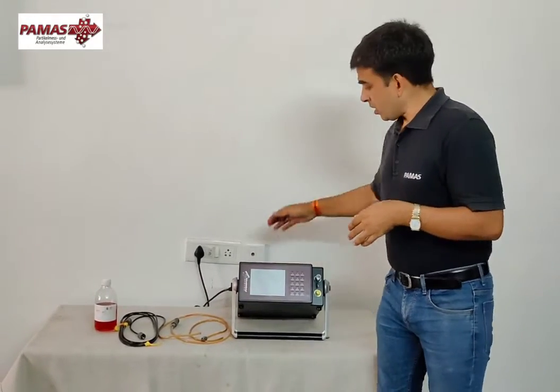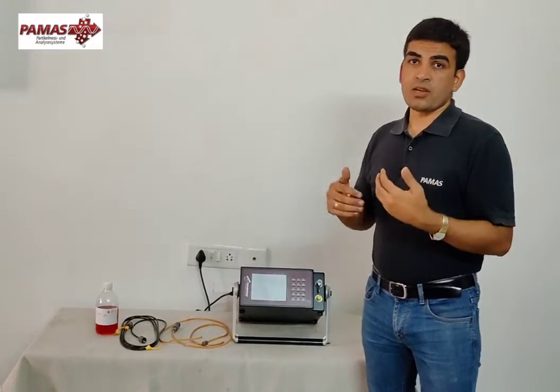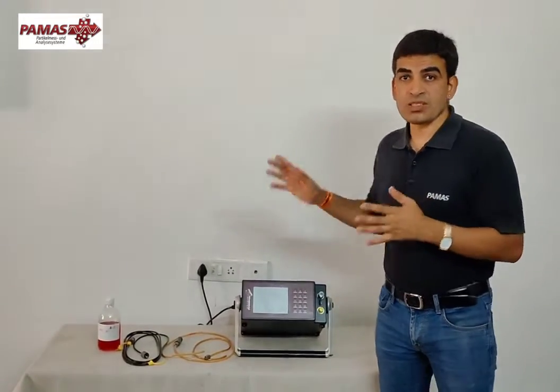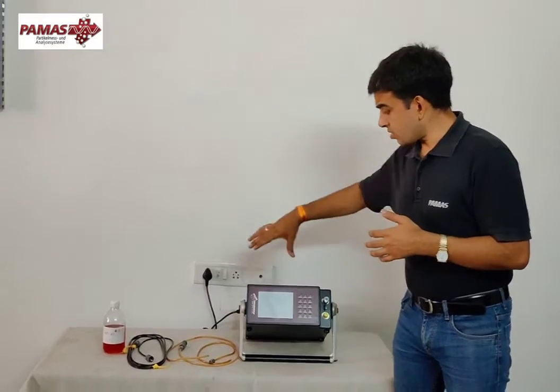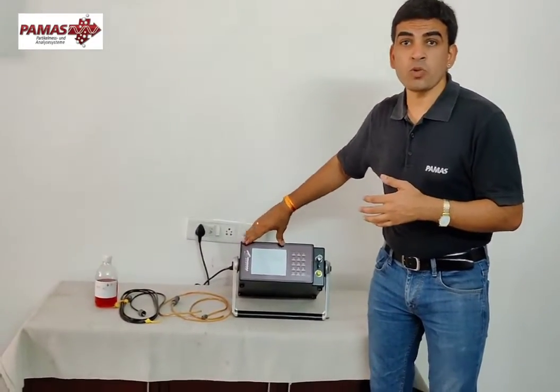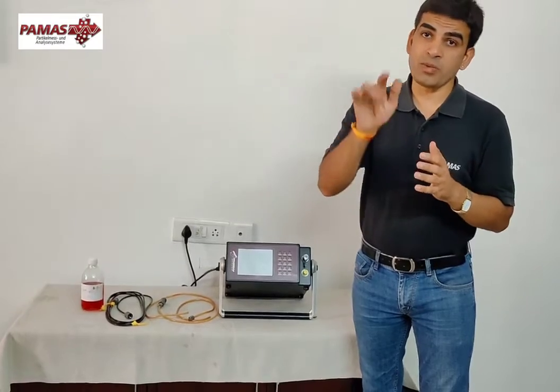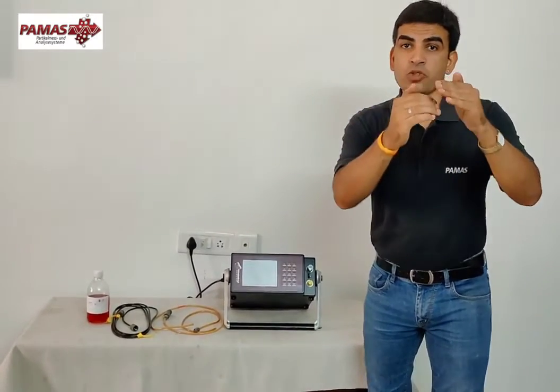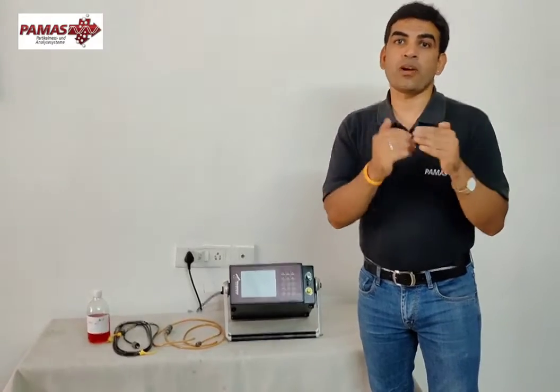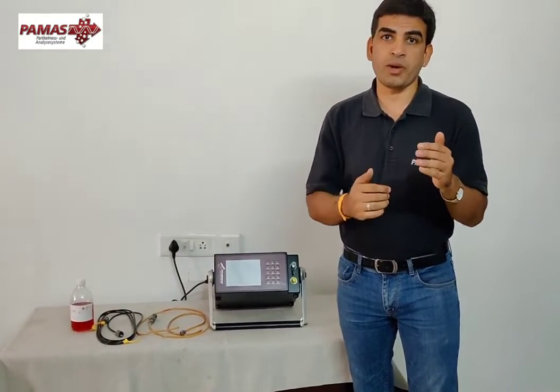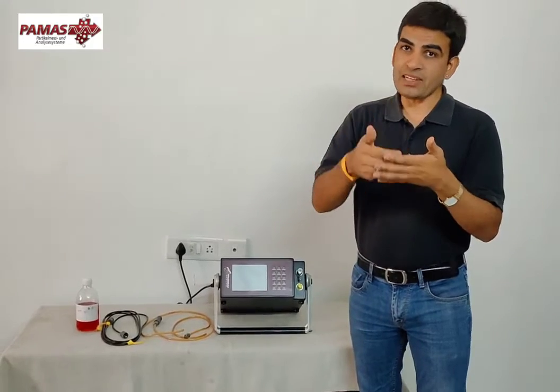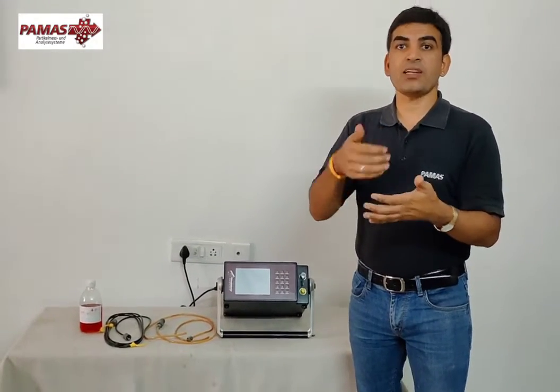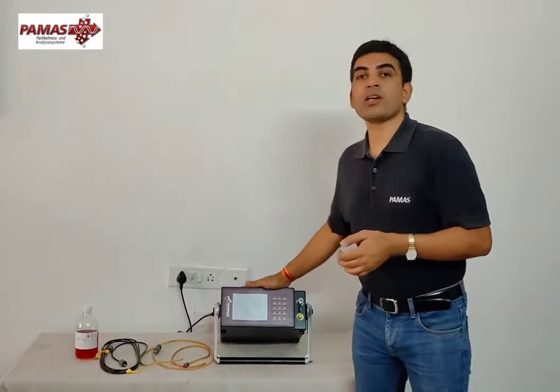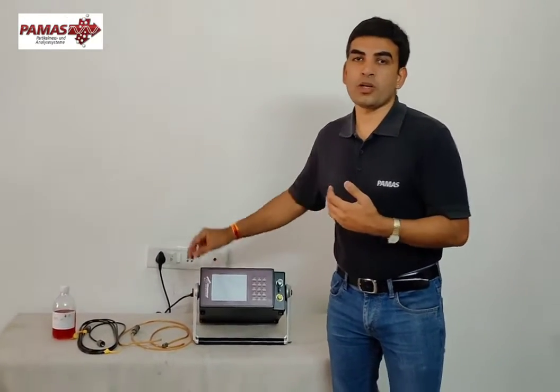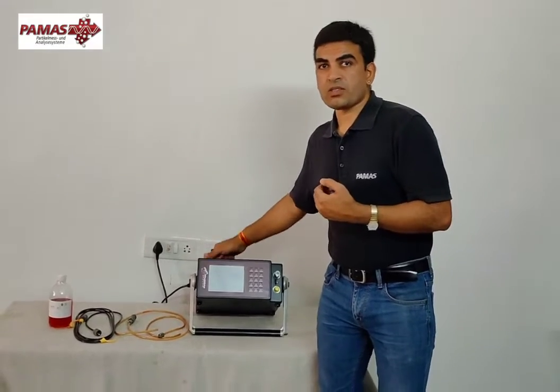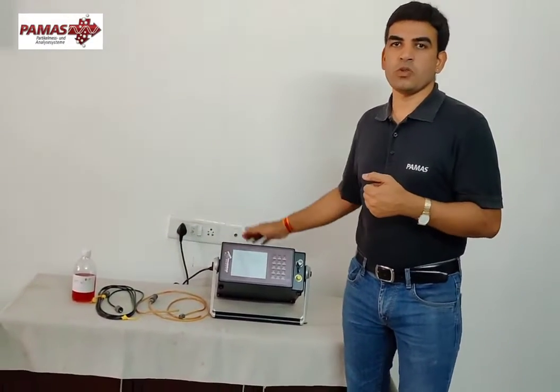This instrument can save up to 4,000 test results. It has 8, 16 and 32 freely selectable channels. What that means is you can have a complete range of particle sizes like 2 micron, 5 micron, 10 micron, 15 micron, 20 micron. You can have all these in 8 channels, 8 sizes, 16 and 32 sizes. It also has another feature: you can transfer the stored data onto your PC through USB.